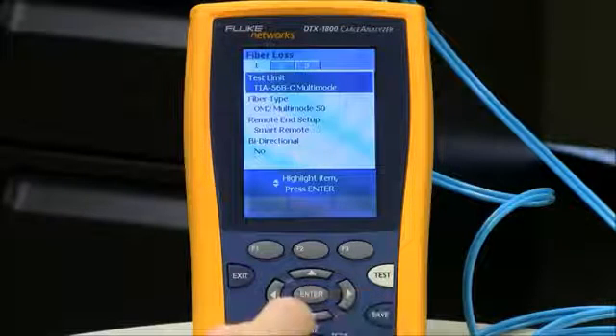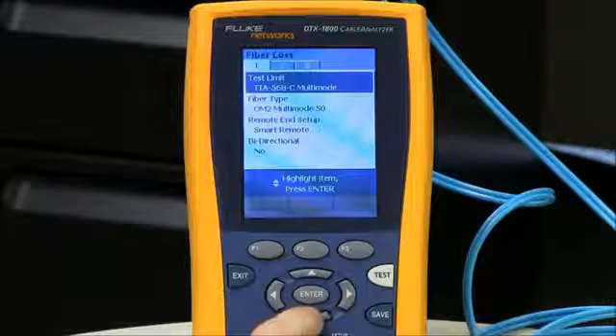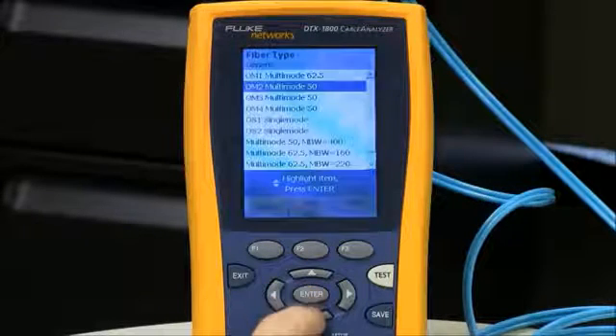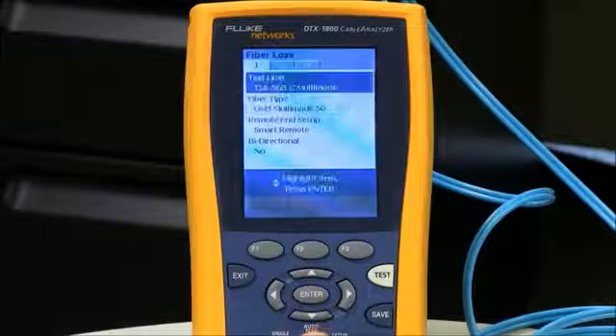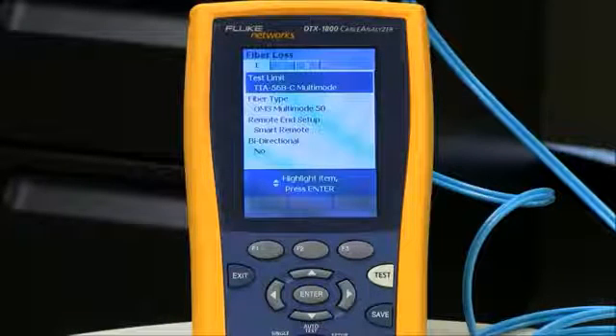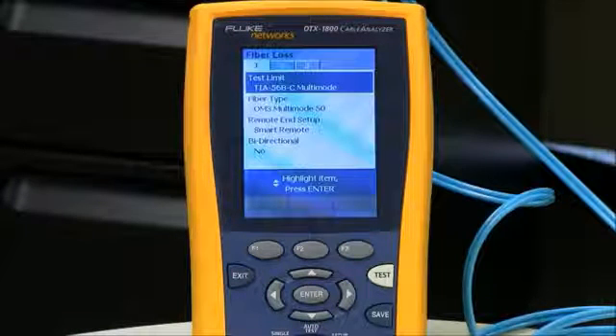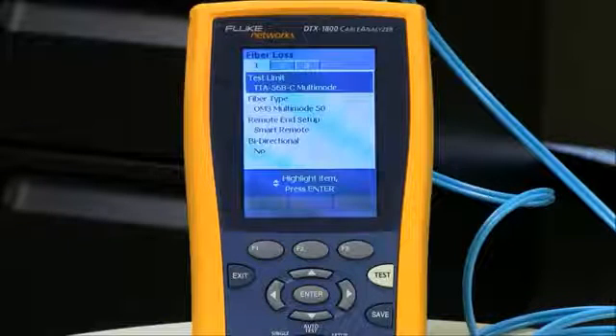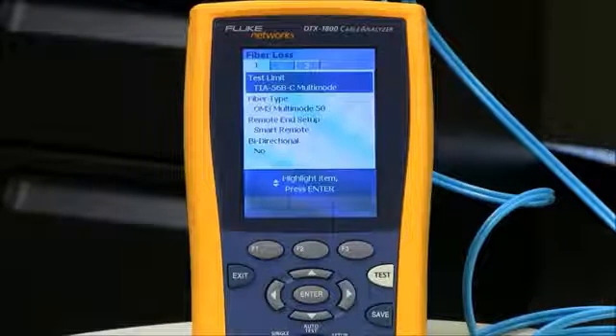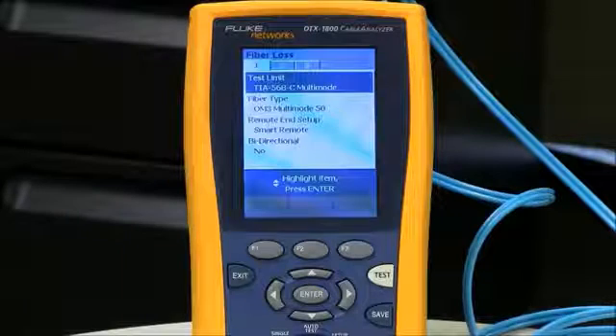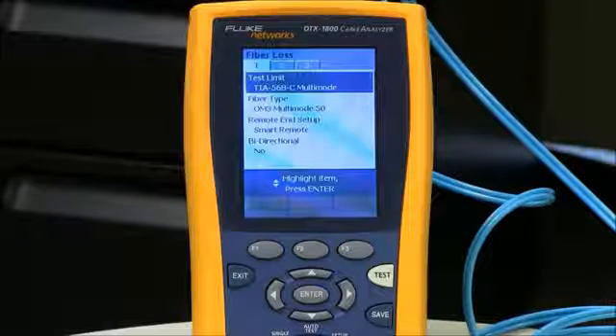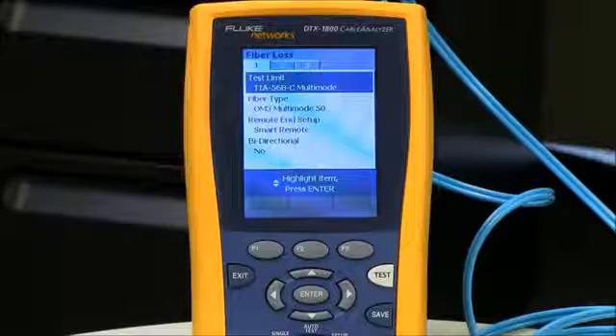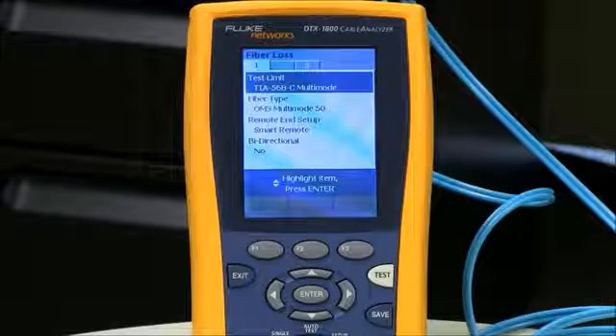My fiber type is currently selected as OM2. Now, that's an issue because I'm testing OM3 today. I need to change that to OM3. Why is that important? At the bottom of your linkware test report, you're going to see a list of supported applications. That list is going to be dependent upon this fiber type selected here. If I'd left it as OM2, any links greater than 82 meters, 10G base SR, would not show up at the bottom. So, this is an important setting.